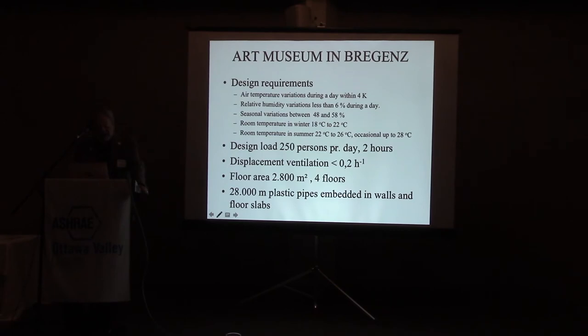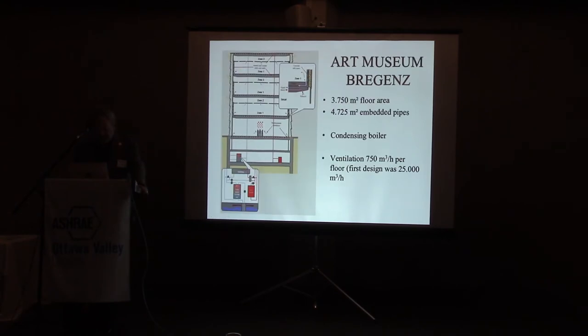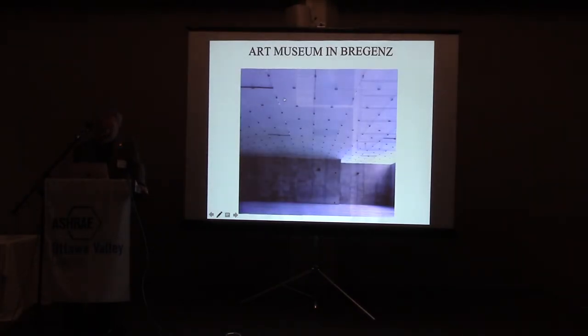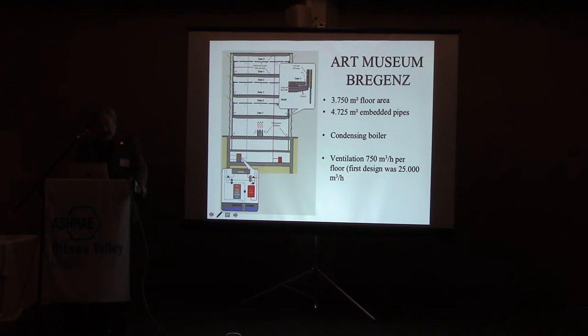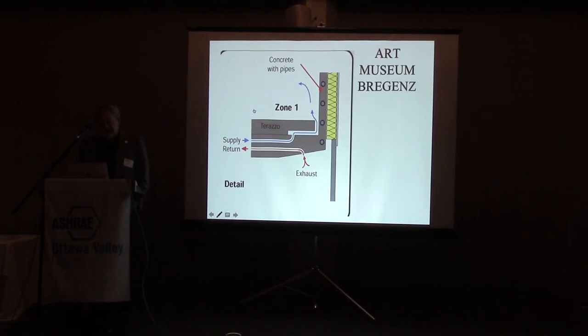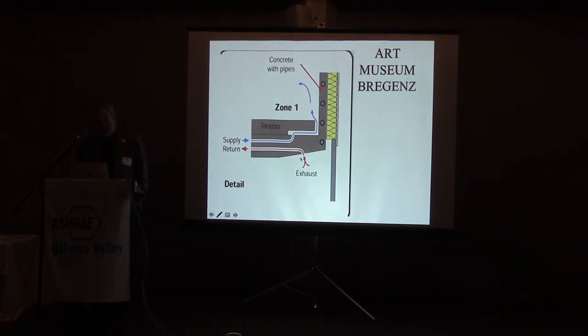And here there was piping integrated in the floors and in the walls. If we look at a drawing here, you see piping has been installed here, here. But you also see here a glass roof above the exhibition area. It looks like this, and it's transparent, like a milky glass. The idea was that the artificial lighting would be above, so you never had any direct light in the exhibition area. Sunshine would also come in here, and you would not have direct sunshine down in the exhibition area. But what was done was that the exhaust air for the ventilation system was taken from this part, which was some of the warmest in the space.